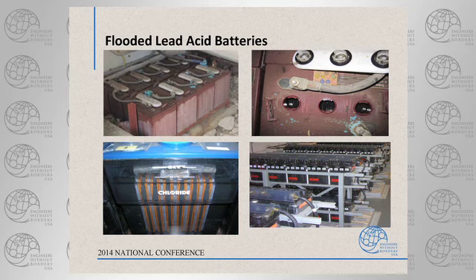Here we're looking in, we pulled the tops off. I did a bad thing here. Notice I didn't get rid of that loose corrosion. I should have. If that gets down into the electrolyte cell, not good. So when you pop these covers, make sure you sweep the corrosion away.